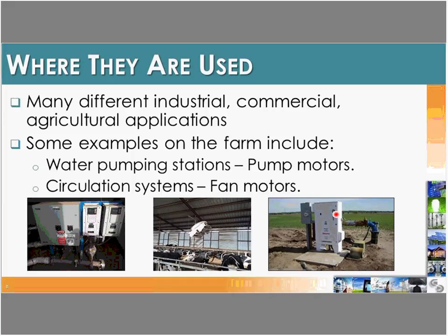On the right is an irrigation pumping plant with an electrical enclosure housing the variable speed drive. Behind it is the motor with the well pump. In this application, we're controlling two different pivot irrigation systems, each with different gallons-per-minute and PSI requirements. We use a pressure sensor and logic to determine which irrigator is active and adjust the well pump speed accordingly as demand increases.